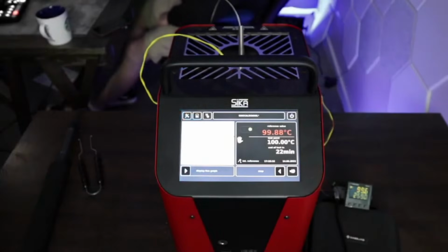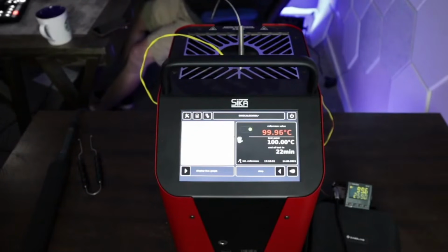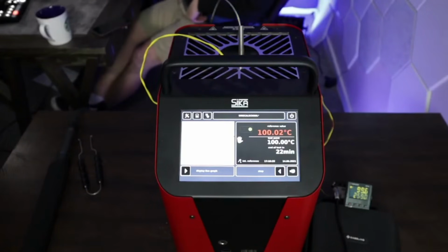So like we were saying, this is an example of a dry well thermocouple calibration. And it's super easy because you just go to the next test point, whatever that is, once you get your measurement. Where are we sitting now? I have to put it larger, I can't see that small. So 99.6 on our makeshift thermocouple, and it looks like it's going to stabilize up there. What's our spec? Our spec is point two. That's for the well. The well is spec to point two.